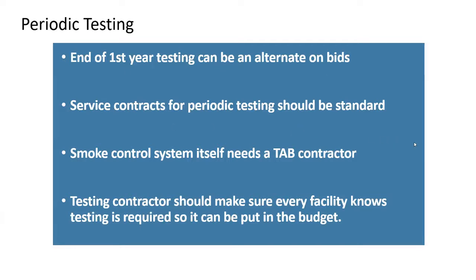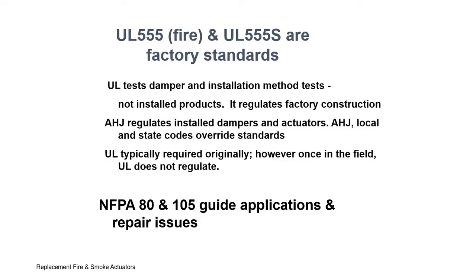Yeah, it can be an alternate in the bids. Low bid is going to tend to win most contracts, so it should be an alternate so that it doesn't price them out of the contract. But if all the contractors are quoting testing, they will start to get some. Yeah. And then, of course, as time goes on, when dampers are tested and anything fails, then they get to work for repairing them, rather than seeing dampers fastened open. All right. Next. I'll let you continue.